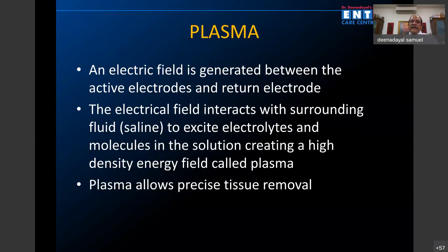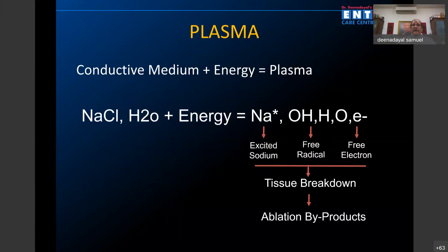An electric field is generated between the active electrode and the return electrode. When the electric field is present, it causes radio frequency waves. These radio frequency waves in the presence of saline excite the electrolytes — the sodium and chloride — causing plasma energy which starts ablating. In simple terms: the conductive medium is saline, energy is radio frequency, it creates plasma, and this plasma excites sodium free radicals and electrons, causing tissue breakdown — what we call ablation byproducts.